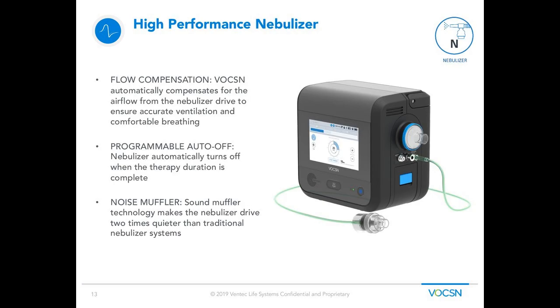The fifth therapy on VOCSN is a high-performance nebulizer. For people living with ALS who need aerosolized medication treatment, VOCSN has an onboard nebulizer. Right now, the traditional method is you have your ventilator and a separate nebulizer device, connected in line with the patient circuit, adding additional flow to the patient. This is very uncomfortable for the patient throughout the treatment, because they're getting not only their ventilation breath but also all the additional air from the nebulizer.